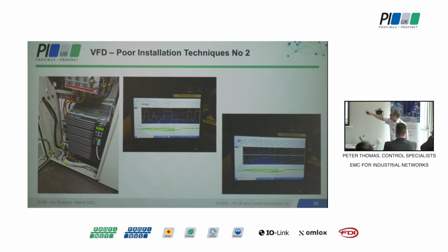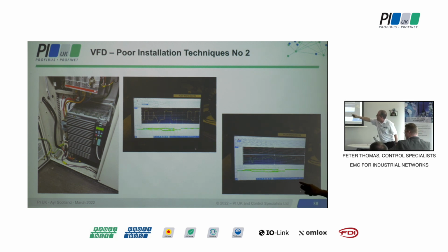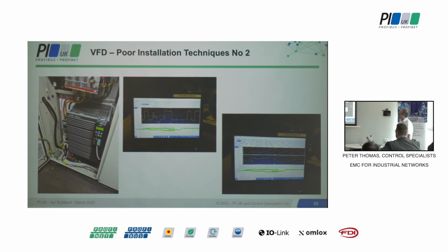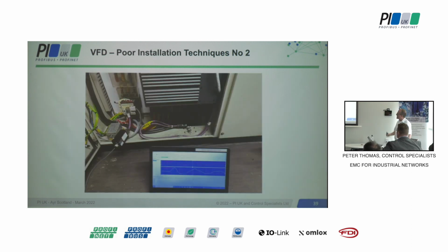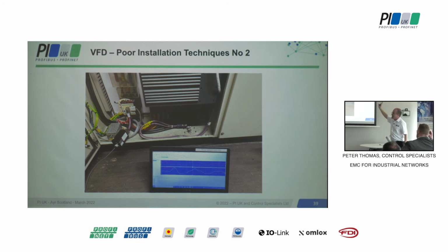Now, we knew it was this drive, but then we could start to have a look. Those black cables going up, they're the three individual conductors for the motor. You've now got capacitive coupling all over the place. So what we did, we took it a little bit further, and what I did was I took the cable off. So this guy now is completely removed. I plugged him into the Profitrace. I just set him up as, for those of you who know what Profi Captain is, a Class 1 Master. I just got him to talk to that guy and we got them to manually start the drive, and that's what I saw.